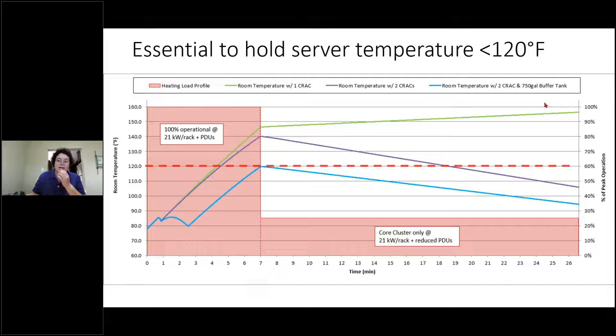And then we had like 8 different emergency failure modes. What if the air-cooled chiller fails? What if the pump fails? What if, you know, we went through everything related to redundancy. We actually wrote commissioning specs in order to test all of it to the satisfaction of the university. But it took us talking to the researchers, the IT guy, every single discipline, in order to get that optimum approach to keep uptime for what they felt was most critical.